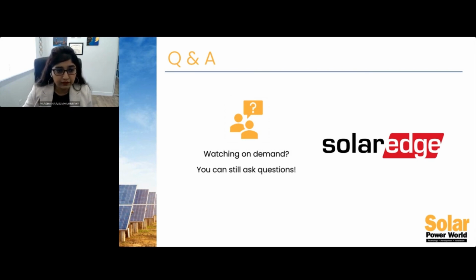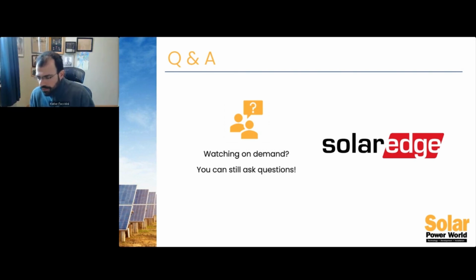Okay. There is, I think, somebody from Brazil here. Hi. Do you think the 690 volts would work in Brazil? Again, if it's a connection behind the meter, you want to avoid any transformer, and you are in a building, probably not. The sweet spot for this inverter is in a plant where you have your collection and transform to medium voltage right there. There is no building connection. However, there are always exceptions to the rule.